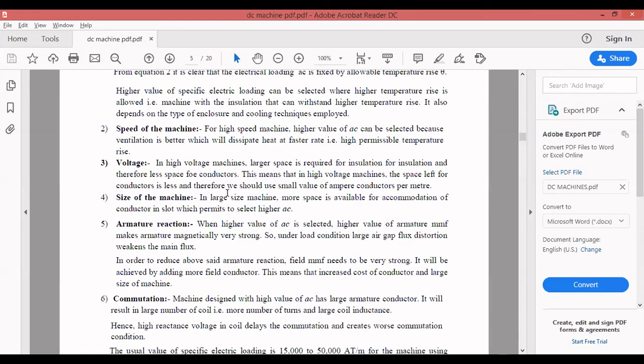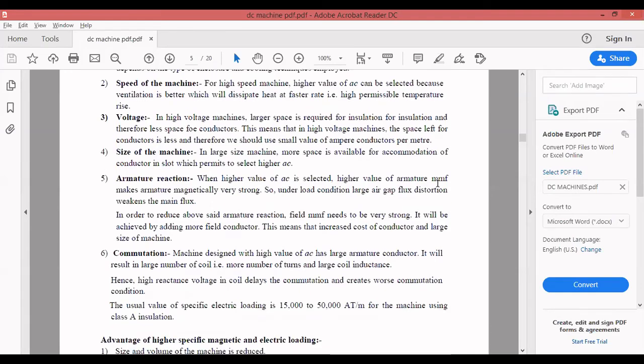Disadvantages of higher specific electrical loading: armature copper loss is increased, commutation becomes inferior, commutation reactive voltage is increased, field copper loss increases due to higher excitation current, and overall temperature is increased. Disadvantages of higher specific magnetic loading: iron loss increased, field copper loss increases, higher magnitude of no-load current, tooth flux density increases, noise in the machine increases, and possibility of magnetic saturation in the iron core increases.